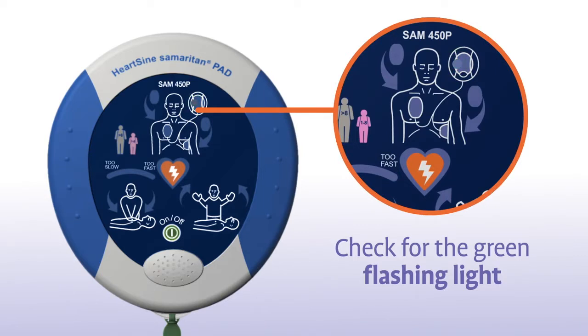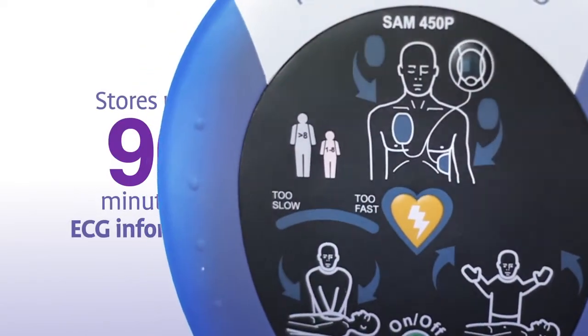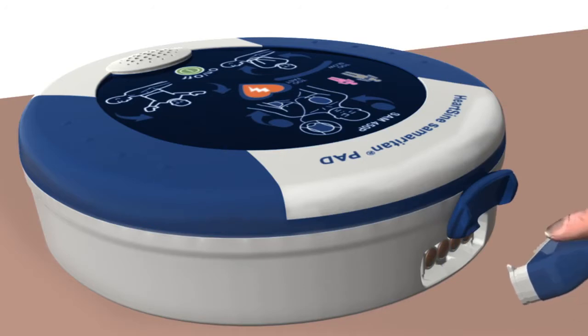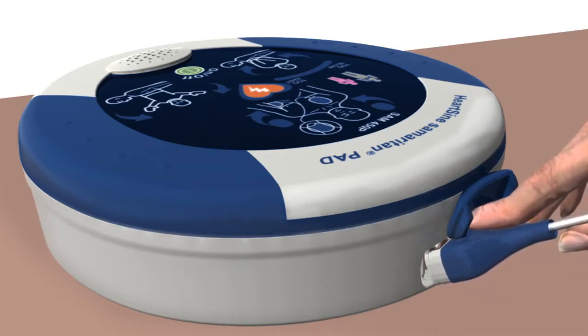The Samaritan PAD stores up to 90 minutes of ECG information after use. Use the Saver Evo software, which can be downloaded from the HeartSine website, and the custom USB data cable to download the event data for a physician who may want the information from the device to formulate treatment decisions.